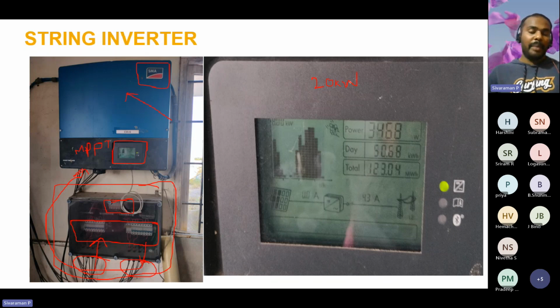Keep in mind, all rooftop PV system inverter ratings will be in kVA only, not in kilowatt. Mostly the rooftop PV system will operate at unity power factor, so 20 kVA is equal to 20 kilowatt. Always remember solar inverter ratings are in kVA, not kilowatt. So if someone says 20 kilowatt, including me, it means a 20 kVA system operating at unity power factor. Always remember this.